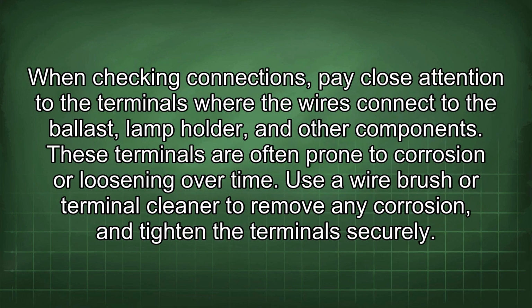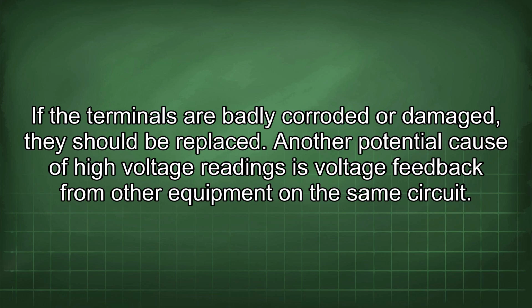When checking connections, pay close attention to the terminals where the wires connect to the ballast, lamp holder, and other components. These terminals are often prone to corrosion or loosening over time. Use a wire brush or terminal cleaner to remove any corrosion and tighten the terminals securely. If the terminals are badly corroded or damaged, they should be replaced.